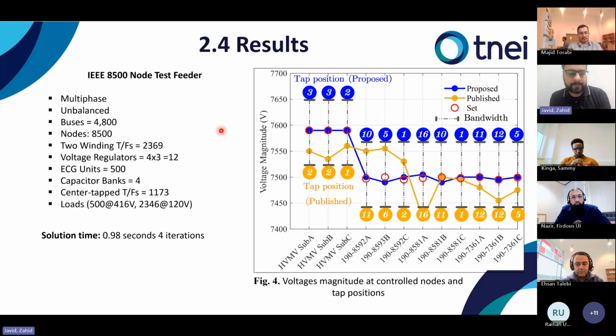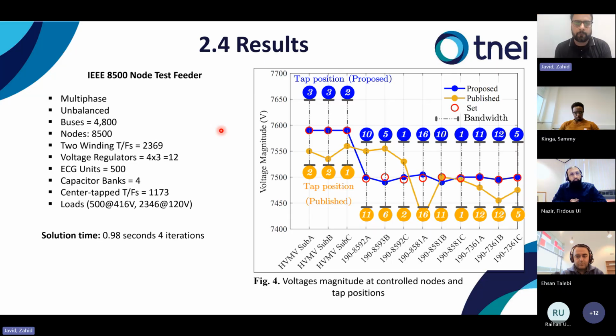To test the boundaries of the solver, we tested it on a very large network, the IEEE 8500 test feeder. This network is multi-phase unbalanced. It has around 4800 buses and 8500 nodes. It has around 2400 two winding transformers and voltage regulators. There are four three-phase voltage regulators, which makes 12 units, and it has 500 ECG units like IBRs, electronically coupled generators, four capacitor banks, and some center-tapped transformers at different voltage levels.